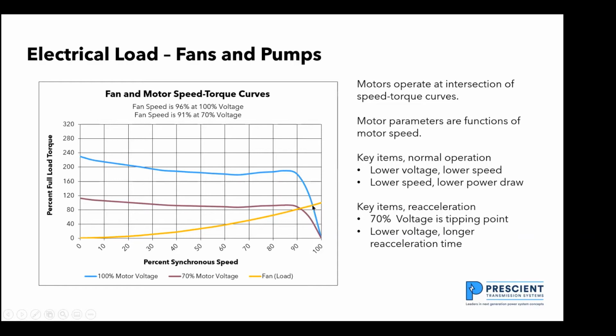So typically I'm looking at induction motors, and at 100% voltage, they're operating somewhere around 96% of synchronous speed. If the voltage drops down to 70%, I'm going to be operating here at 91% speed. So the power demand of a motor is a function of the terminal voltage you put on the motor, and the terminal voltage determines the intersection of the fan curve and the motor curve.